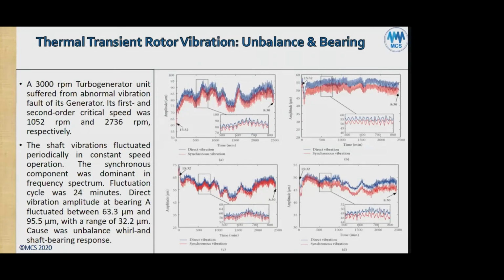In fact, that's something we should discuss now. What's the acceptable fluctuation for an electrical machine? Let's say it's a 10 megawatt generator, 20 megawatt, or 100 megawatt generator. In my experience, 10 microns is perfectly fine. Up to 12.5 microns, half a mil, is perfectly fine, nothing at all, not worth any trouble. However, if you're going up to 1 mil fluctuation and above, which is 25 micron or more, there's something wrong.